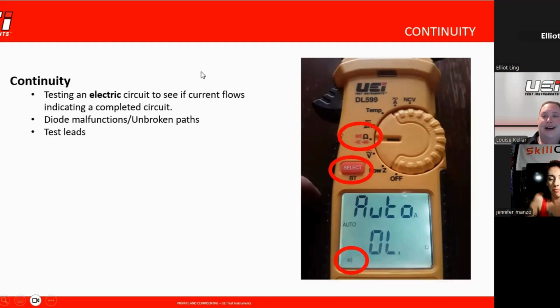Continuity testing is huge. Not only do we want to make sure a circuit is flowing correctly, we want to test the test leads. If you're not regularly testing your test leads, you may be doing yourself a disservice, and it's a good habit to form. I literally can't use my meter in continuity mode until I've tested my test leads, because unfortunately test leads can break. We throw them in our bags, they get wrapped around things. If we have our meter set to continuity and touch the two tips of our leads together, you should get a nice loud beeping sound that tells you you're good to go.